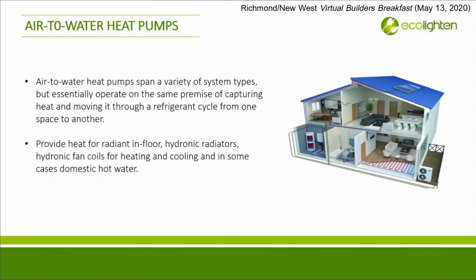The other option is an air-to-water heat pump. It absorbs heat from the outside air and rejects it to water. As the province goes the same direction for GHG emissions, air-to-water heat pumps will become increasingly the only option available for houses that insist on radiant floors.